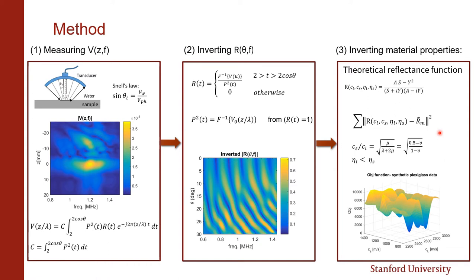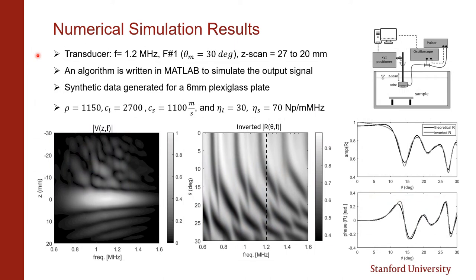In this process, we have chosen the four variables as the unknown, and the global search method is used for optimizing the objective function. We have designed an acoustic microscopy system to operate at a low frequency range around 1 MHz. It's formed by an in-house manufactured focus transducer made of a spherical piezoelectric shell with F1.